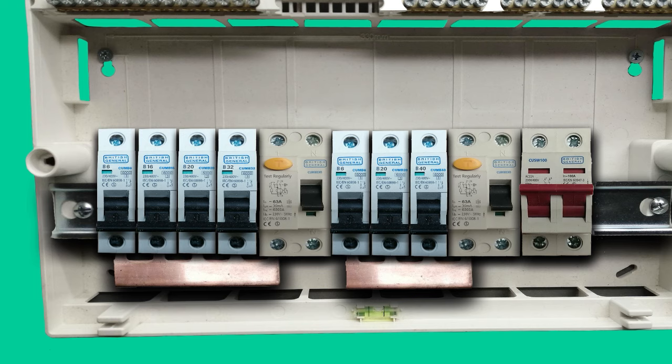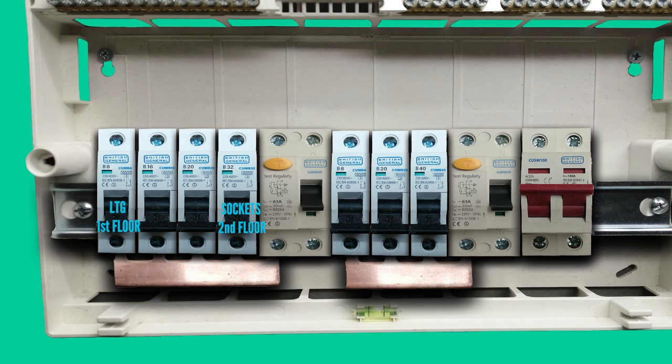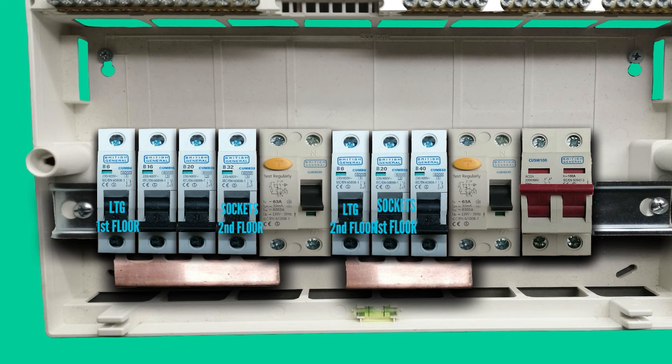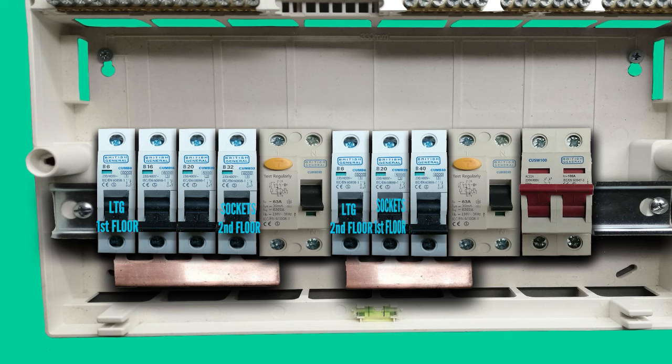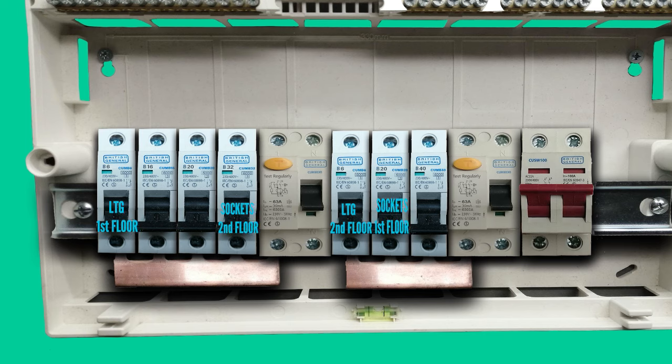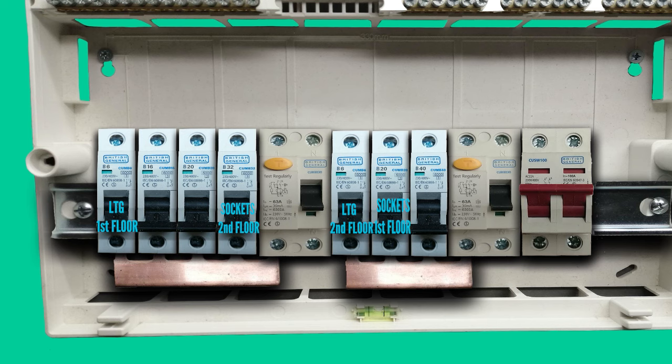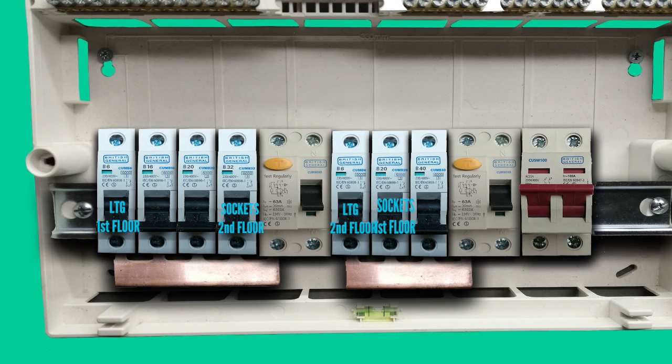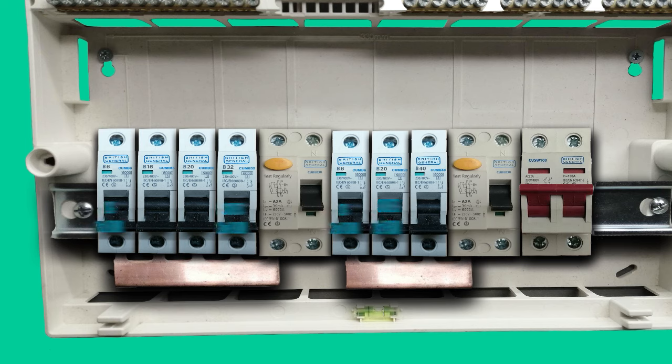Why do we need two RCDs in this consumer unit? In case of a fault in one of the circuits, you can still get the power or light on every floor in the house. The electrician always fits the lighting circuit from the first floor and the power circuit from the second floor on one RCD, and the lighting circuit from the second floor and the power from the first floor on the second RCD. So in case of a fault and disconnection of an RCD on overloaded circuits, you still have power or lighting as not all of the circuits are on one RCD. So if there is no lighting on one floor but you have power in socket outlets, you can always plug a freestanding lamp to the socket outlet and check for faults.